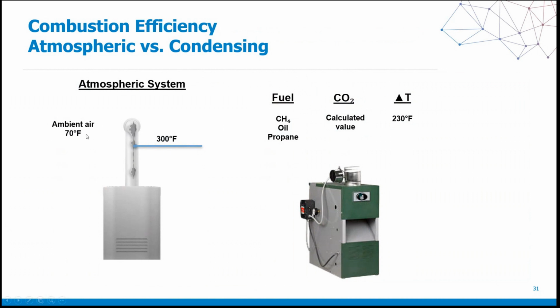So when we look at this example, again, ambient room air, say we're in the furnace or boiler room, and say it's 70 degrees. That figure gets subtracted from our stack temperature of 300 degrees, and then we have a delta T of 230, or change in temperature. These three things, your analyzer will take, calculate them, and produce your combustion efficiency, whether for an atmospheric system, whether it's 78% or 88%, it doesn't matter. It will take these three criteria and produce your combustion efficiency.